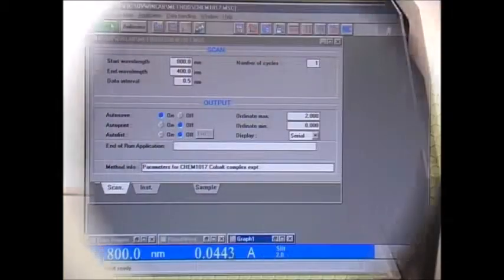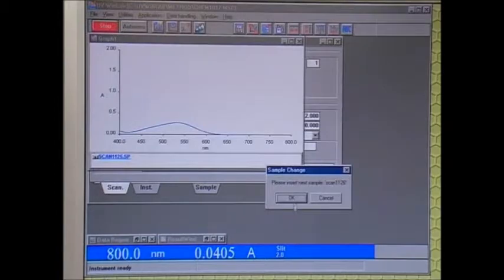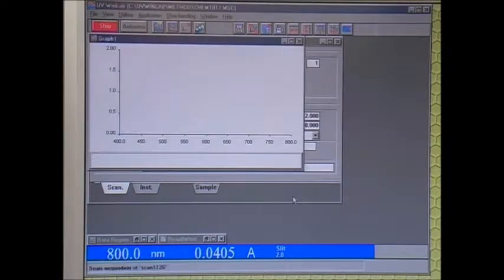The wavelength range required and the scanning speed must be programmed in the computer that controls the instrument. The spectrum appears on the screen and the data is saved in the computer.